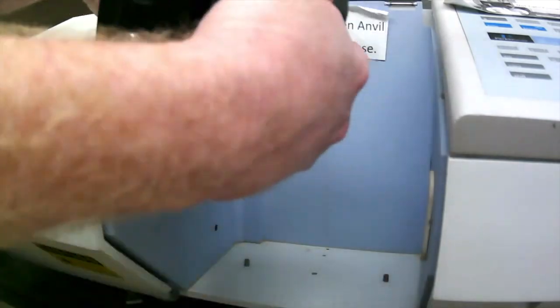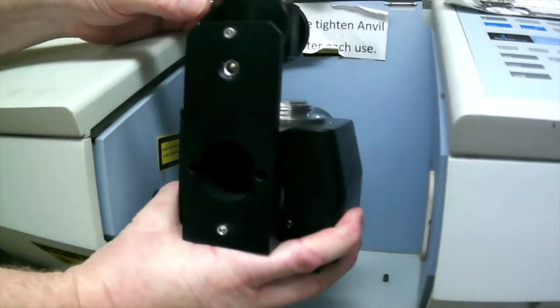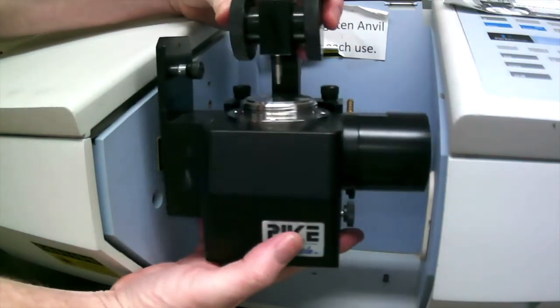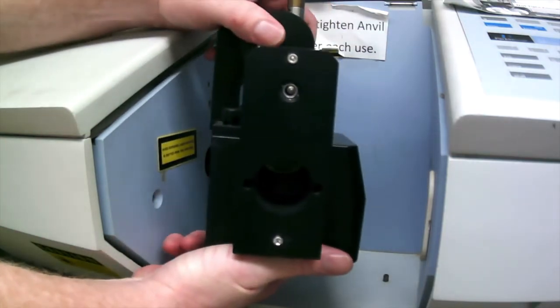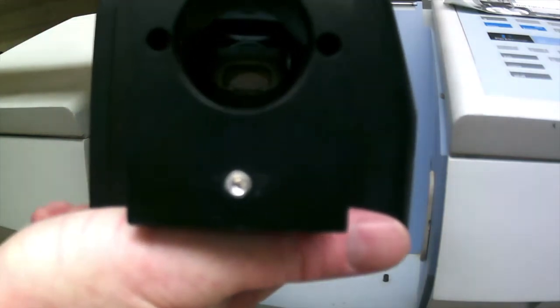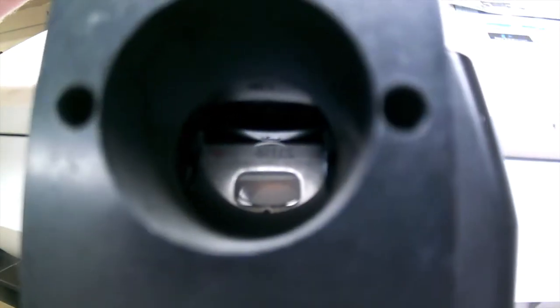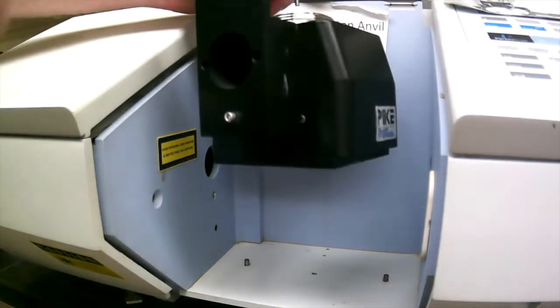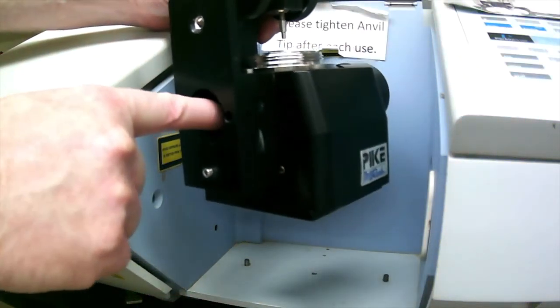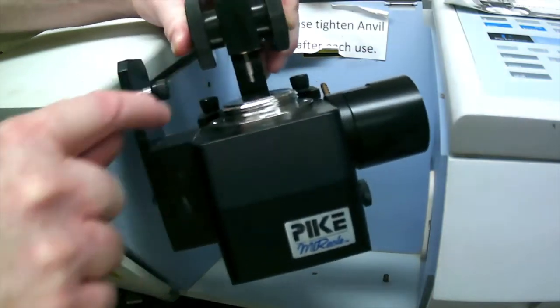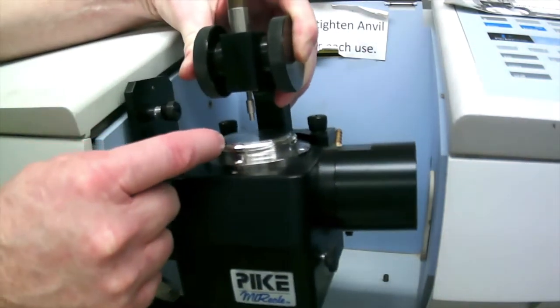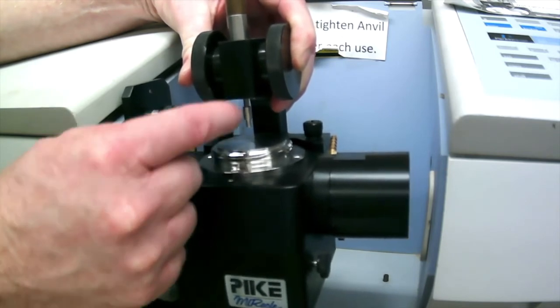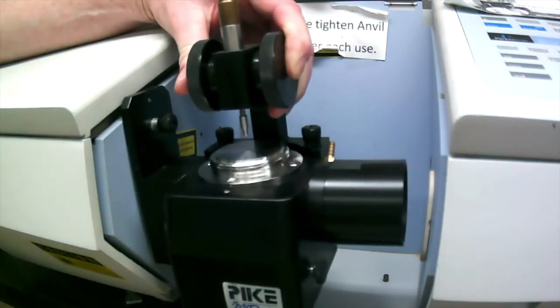Okay, so this is our ATR adapter, right? Looking at it this way. When I twist it sideways, you can probably see inside of there, there's a mirror. See, that's a mirror right there. That mirror that's in here will have the infrared light hit off the mirror and then into the zinc selenide crystal, and it does total reflectance. It bounces back and forth through there, kind of like a fiber optic cable.